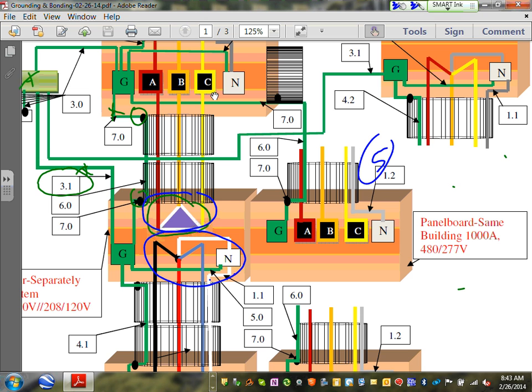Does it make sense? Look at the delta wires and the Y wires. Do you see any connection between the wires coming to the delta, to the 480 here, and the wires coming to the 208/120 side? Is there any connection? None, except through the ground, which is okay. If there is no connection between the primary and secondary of the transformer, the NEC code book calls this a separately derived system. You're going to hear the words separately derived system.